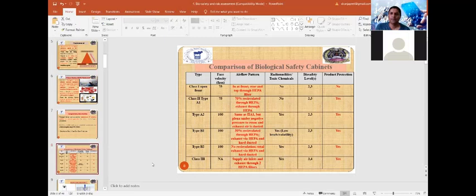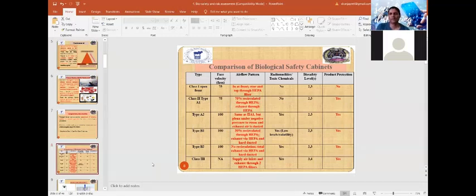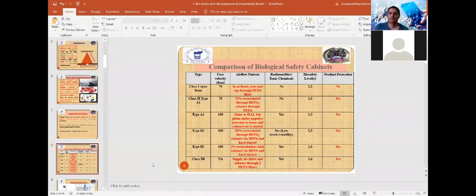Class 2 biosafety cabinets are a higher, more protective version and include Types A1, A2, B1, and B2. Type A1 has a face velocity of 75 fpm, and 70% of the air entering the cabinet is recirculated through HEPA filters, reducing the load on them. Exhaust air is also through HEPA filters. It may be used in BSL-2 and BSL-3 laboratories and provides product protection.